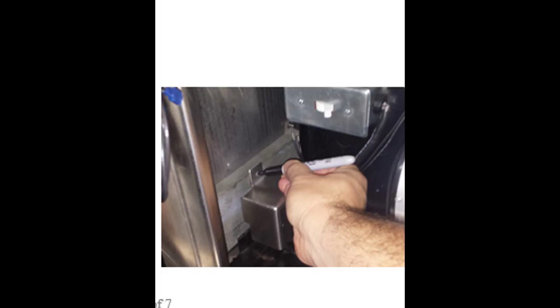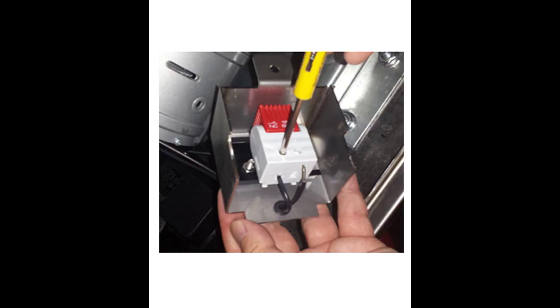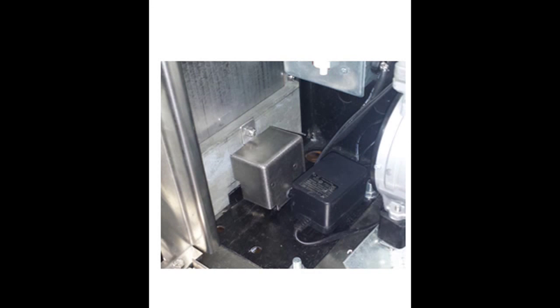With the lower blocker plate installed, position the thermostat and mark the mounting hole location. Remove the blocker plate and drill a 1/4 inch hole at the marked location. Before permanently mounting the thermostat to the blocker plate, pass the power cable with the two black wires from the heater assembly through the grommet in the thermostat bracket and connect as shown. After wiring the thermostat, install the thermostat and the bracket on the blocker plate and reinstall as shown.